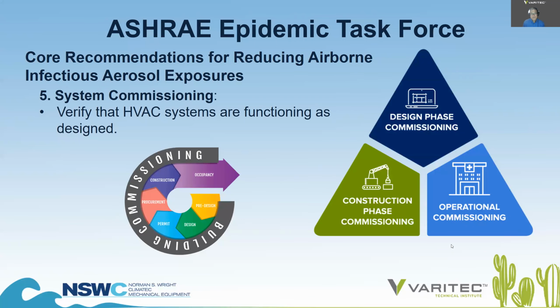And then, of course, number 5 is system commissioning. Do we have a means of testing out, per the checklist that ASHRAE actually does provide in the recommendation guidelines for the reopening of buildings? Are these systems operating? Is the outside air damper opening up to make sure that the building is getting at least the minimum outside air as prescribed by ASHRAE Standard 62.1? That's a big one.